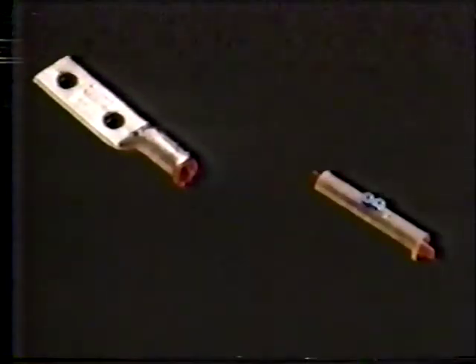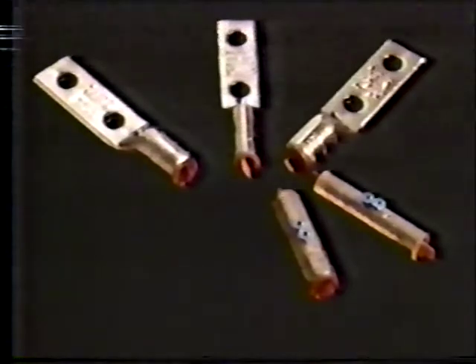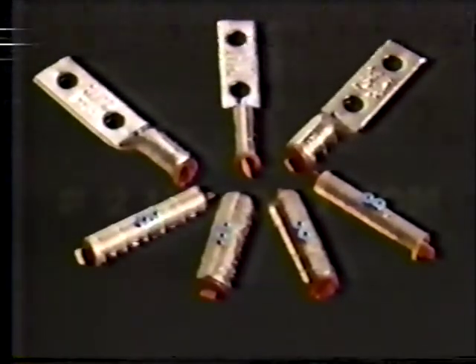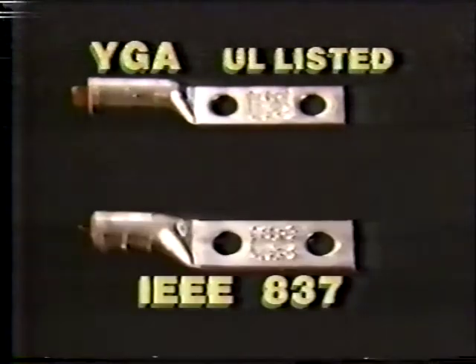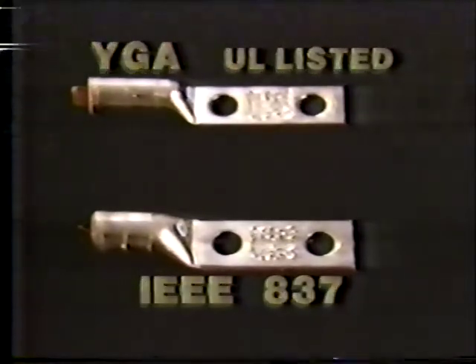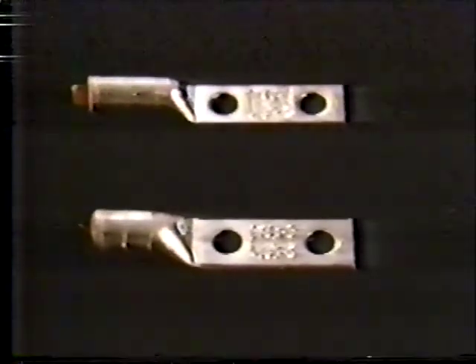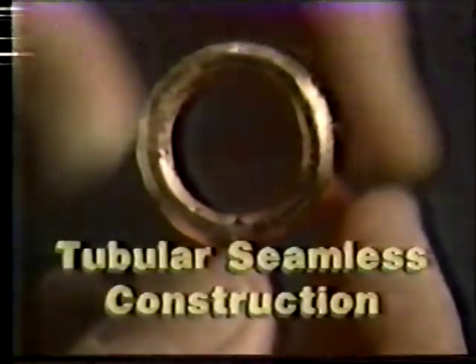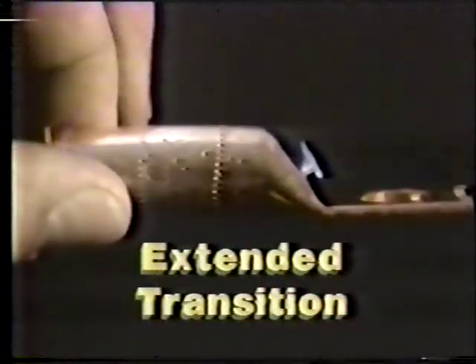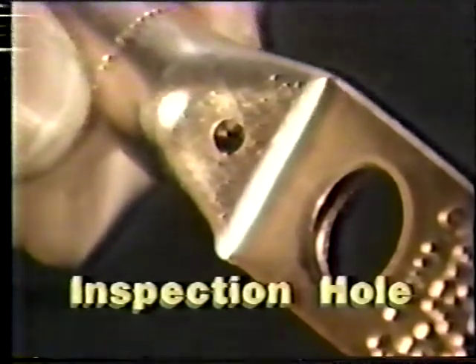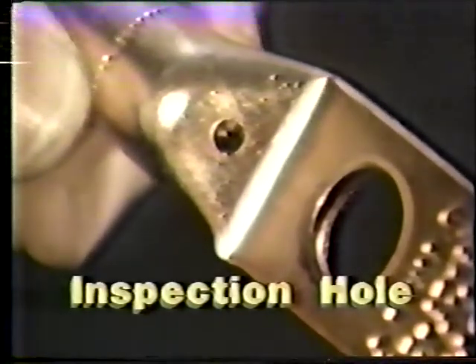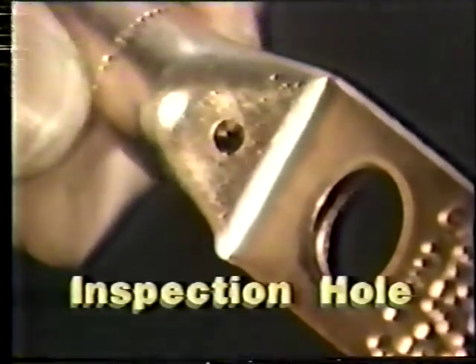Because terminals and splices are required for most ground system installations, Burndy provides terminals and splices to accommodate number 2 through 500 MCM conductors. Burndy's terminal line consists of both standard duty UL listed models and heavy duty designs to meet IEEE 837 requirements. These grounding terminals incorporate many of the features found throughout our Hydent line, such as a tubular seamless construction, an extended transition, and an inspection hole to confirm that the conductor is fully inserted into the connector barrel. In addition, Burndy ground terminals are pre-filled with our Penetrox oxide inhibiting compound.